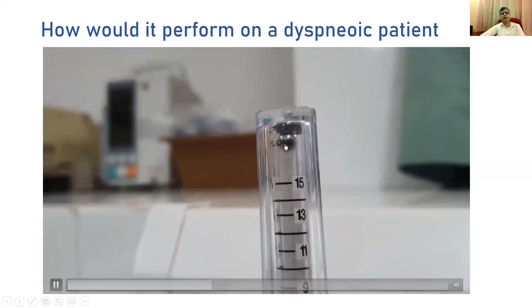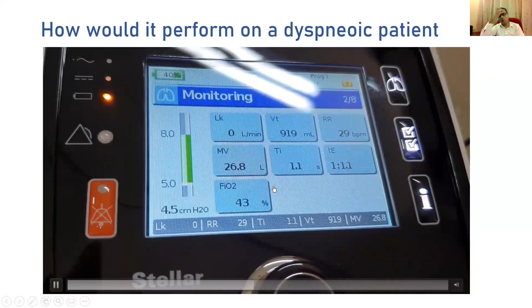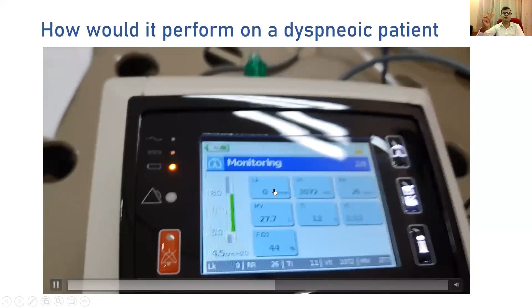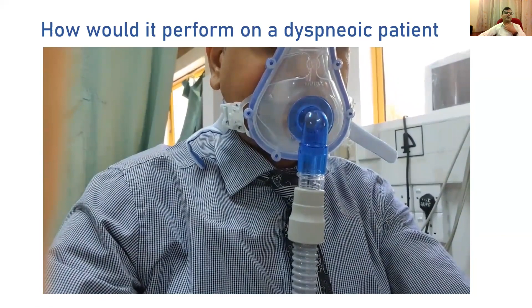If I increase the flow, it floods the system. So I'm getting more than 15 liters now. We'll see what happens from 35 to... here you can see it's 44 now. It's actually getting a little bit more FiO2 if you use it to the flood level. But I usually recommend using a 30 liter per minute flow meter. Here I'm using the 70 liter one, but generally you should not use 70 liters because it can damage the device. I tried up to 70 on my device, but here I'm demonstrating only up to 30-40 liters to see what happens.